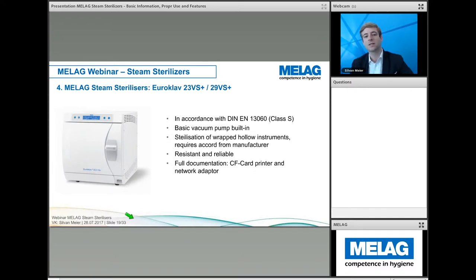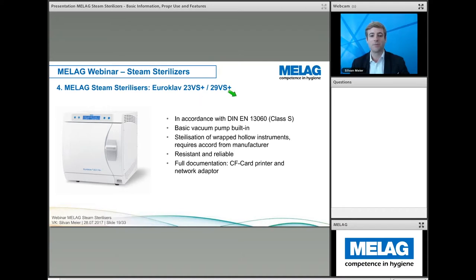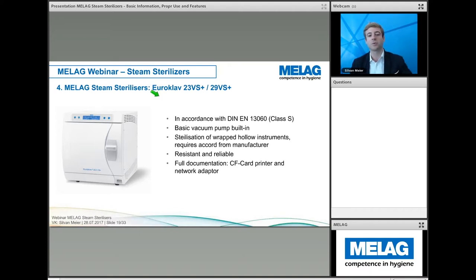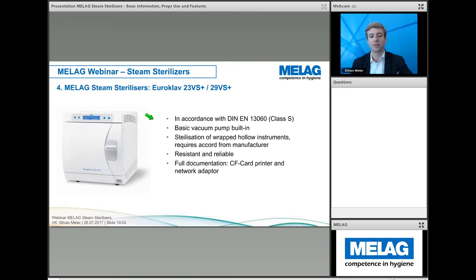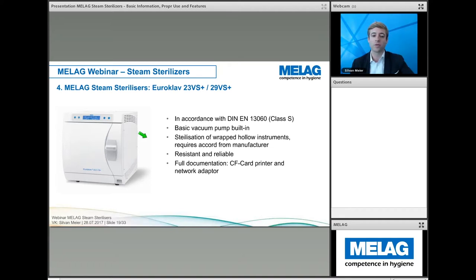Also in the Class S category are the Euroklav 23 VS Plus and 29 VS Plus. Both comply with EN 13060 and have a basic built-in vacuum pump enabling a first vacuum cycle. This allows wrapped hollow instruments to be sterilized, though it requires agreement from the instrument manufacturer. The unit is very resistant and reliable with a long lifespan, and full documentation is possible.